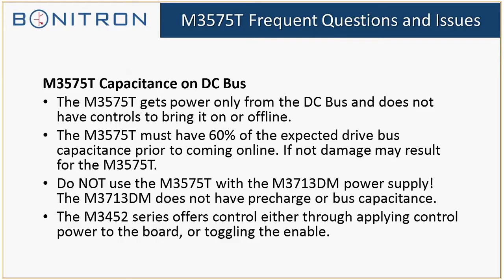A simple diode bridge, an example of that would be our M3713 DM power supply. That DM is basically a simple bridge rectifier, and there's no real capacitance in that unit. And the M3575T will basically harm itself if it's connected to the M3713 DM power supply. As far as being connected directly to drives, the M3575T has no problems because drives have their own DC bus filter capacitance, and as long as the 3575T is sized to the drive, there's absolutely no issues once the drive brings itself up.